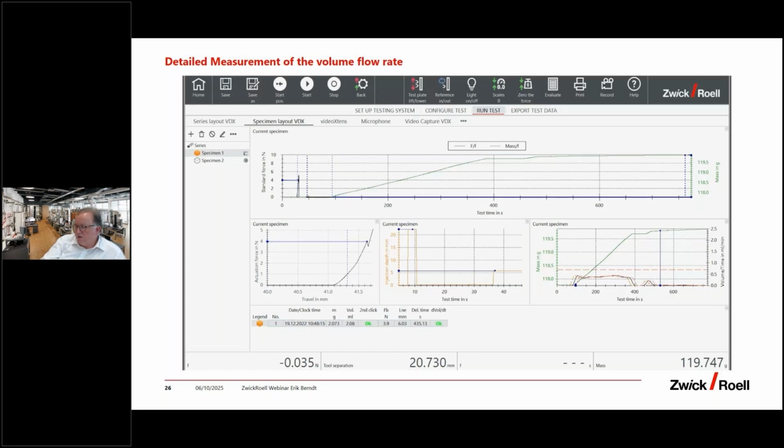There could be an electronically driven system. There could also be some different phases on injection, and the testing system must match the intended use of the product. But for sure, there are different features which have a little bit of difference to the autoinjector, and we cannot directly use perhaps the normal autoinjector machine for this long time. There are different requirements on this.